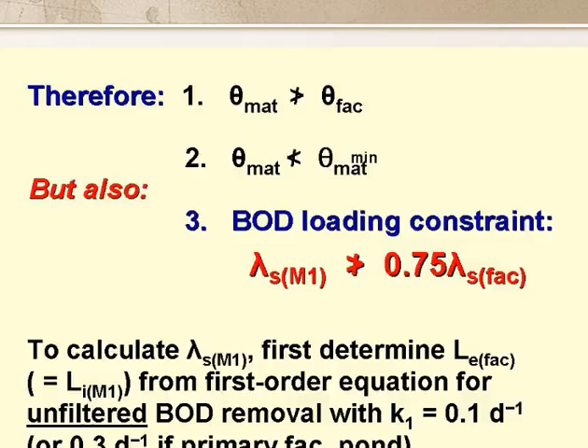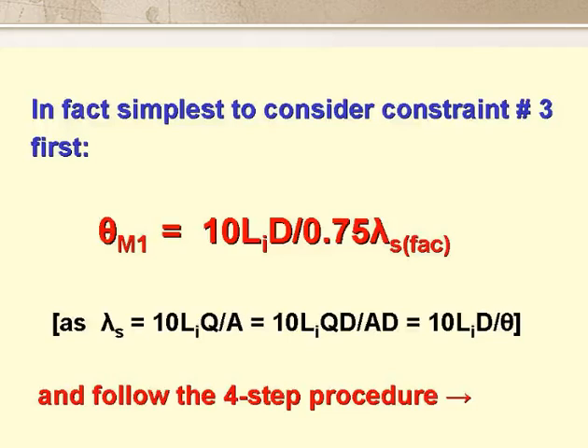We should also consider a BOD loading constraint. The BOD loading on the first maturation pond can't be greater than that on the preceding facultative pond, and it's better if it's quite a bit less. I prefer to say that the loading on M1 can't be more than 75% of the facultative pond loading. To calculate lambda SM1, we first determine the effluent BOD from the facultative pond using the first-order equation for unfiltered BOD removal, with K1 equals 0.1 day to the minus 1, or if it's a primary facultative pond, with K1 equals 0.3 day to the minus 1. It's best to consider this loading constraint first and determine the minimum value of theta M1, then follow the four-step procedure.